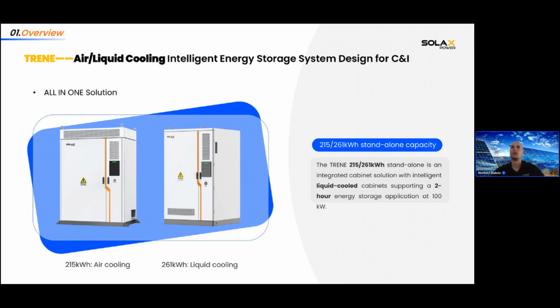The other one is the TRENE. It's AC coupled, so you don't have an inverter in it because you can connect it to the AC grid. And you have a PCS inside the ESS. So there are two versions of it. The 215 kilowatt hour, it's the air-cooled version. And then the 261 kilowatt hour, it's with liquid cooling. And here, the liquid cooling will be available later this year, in Q4 probably. So then you can order it from us, and you can already order the air-cooled version. So these two are from the TRENE. Both have a PCS inside it, but we will check it here.